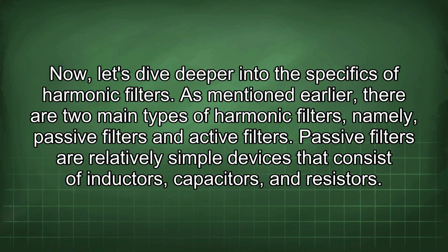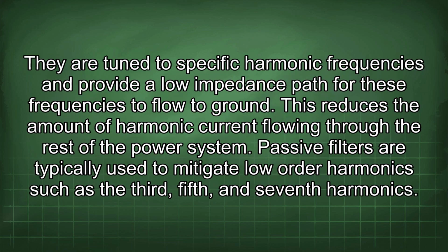As mentioned earlier, there are two main types of harmonic filters, namely passive filters and active filters. Passive filters are relatively simple devices that consist of inductors, capacitors, and resistors. They are tuned to specific harmonic frequencies and provide a low impedance path for these frequencies to flow to ground. This reduces the amount of harmonic current flowing through the rest of the power system. Passive filters are typically used to mitigate low-order harmonics such as the third, fifth, and seventh harmonics.